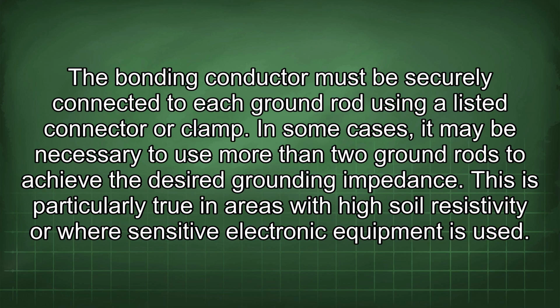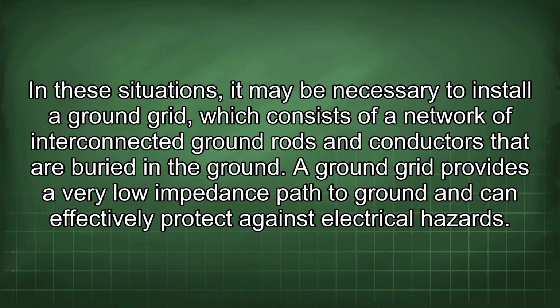In some cases, it may be necessary to use more than 2 ground rods to achieve the desired grounding impedance. This is particularly true in areas with high soil resistivity or where sensitive electronic equipment is used. In these situations, it may be necessary to install a ground grid, which consists of a network of interconnected ground rods and conductors that are buried in the ground. A ground grid provides a very low impedance path to ground and can effectively protect against electrical hazards.